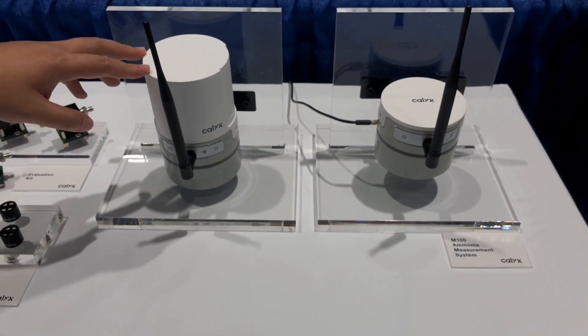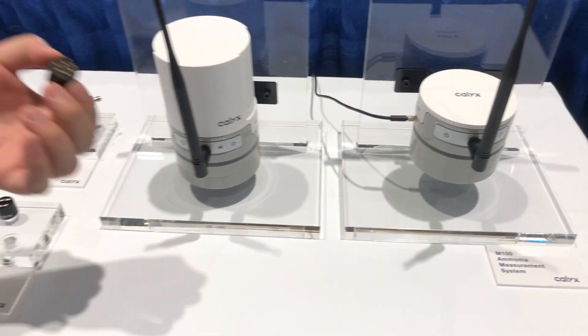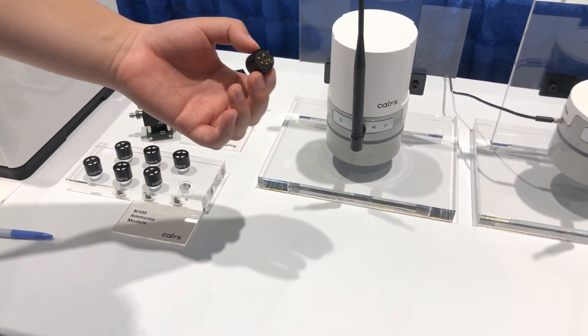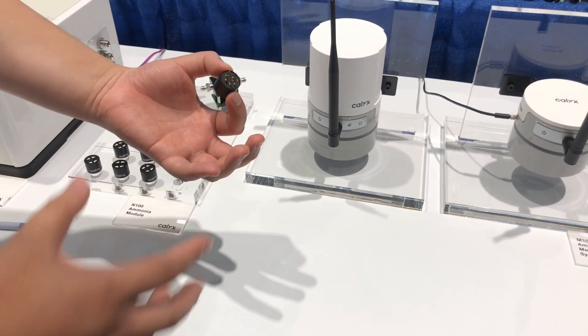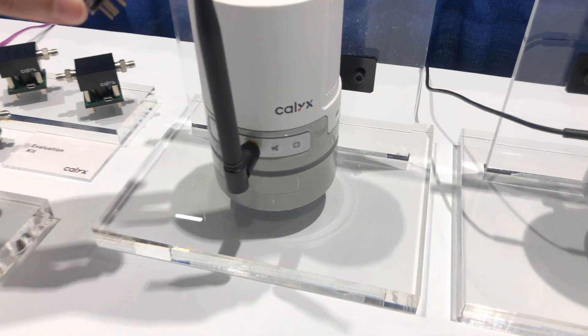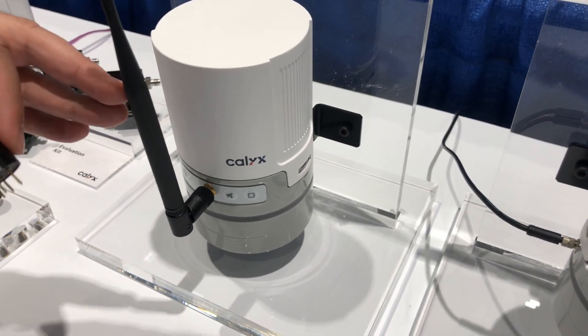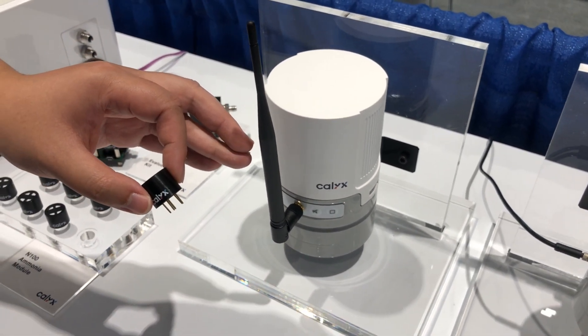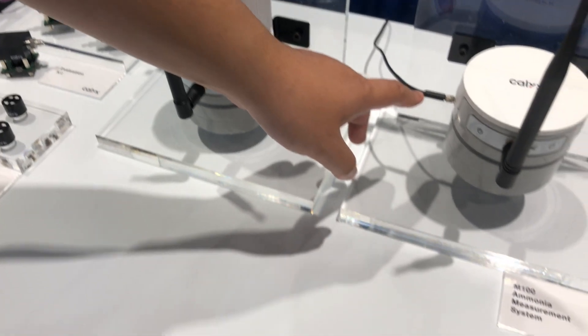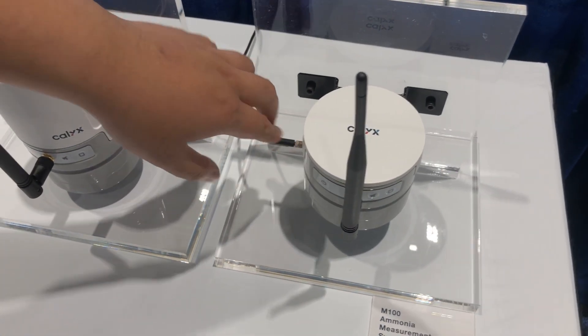This is our M100 ammonia measurement system. We take the ammonia module and develop the entire system around it. We make the entire system waterproof — it's IP65 water resistant. We include a battery pack so it will last multiple years in the field without AC power. We also have a wireless communication method to transmit data wirelessly, and there's also an option to connect it to AC power if needed.